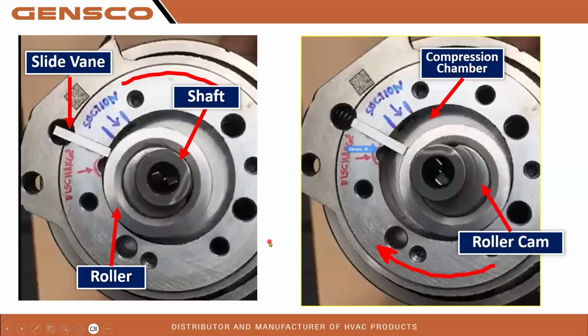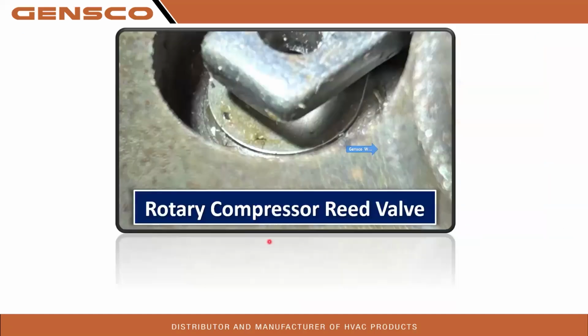This is the cam that the roller rides on. You see that it puts the roller off center of the shaft so that it can wobble around inside the compression chamber and, with the slide vane, produce compression. And the oil pump, you can see the two little vanes that pick up oil from the bottom of the compressor to distribute it to the oil ports in the moving parts section, such as where the cam comes in contact with the roller and the shaft comes in contact with the bearings. This is the slide vane that would be above that discharge exit from the compression chamber.